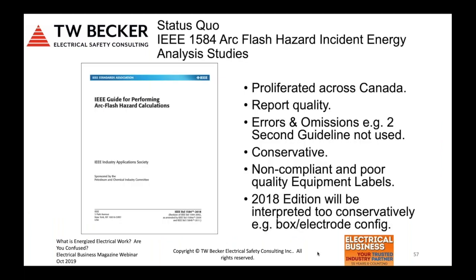So one last thing is related to status quo. I think there's a couple more slides here. I wanted to say that the IEEE 1584 standard, first published in 2002, has been published in its new edition in November 2018. So that's 16 years later. There are some significant changes in this new edition of IEEE 1584. The studies have proliferated across Canada. From the previous edition, I'm concerned about the report quality, errors and omissions, for instance, the lack of the 2-second guideline being used, conservative determination of the parameters as the inputs to the studies, and then non-compliant and poor quality equipment labels have been issued historically.